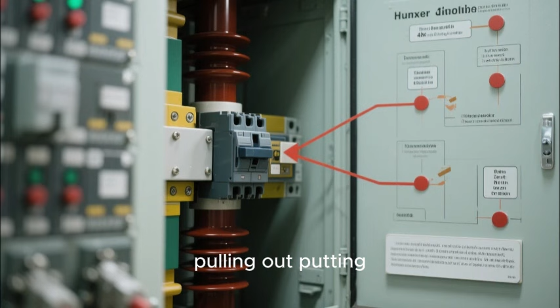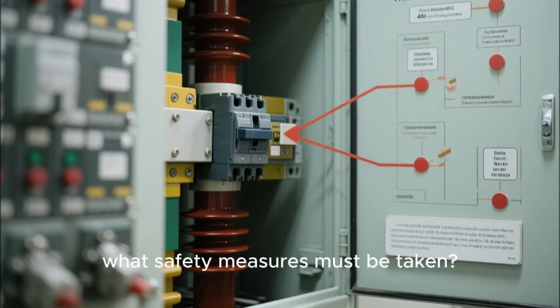When working on-site, pulling out / putting into the operating position of high voltage switching equipment, what safety measures must be taken? Answer: wear high voltage insulating gloves, high voltage insulating boots, or wear high voltage insulating gloves. Stand on an insulating chair / mat suitable for the voltage level. Requirements for remote operation? Answer: performed by 02 people, 1 supervisor, 1 direct operator, except in the case of emergency troubleshooting.